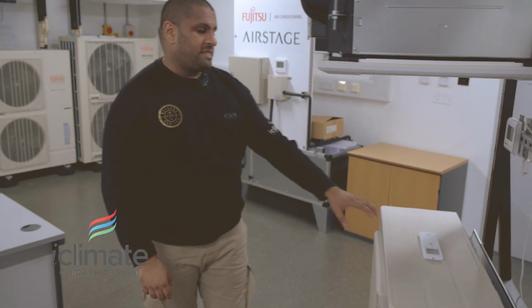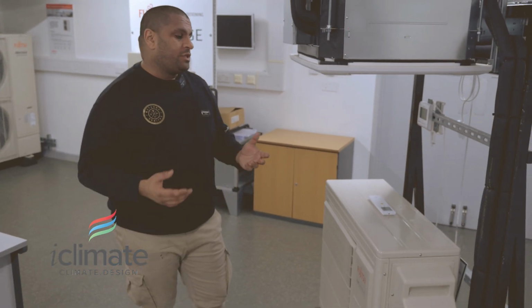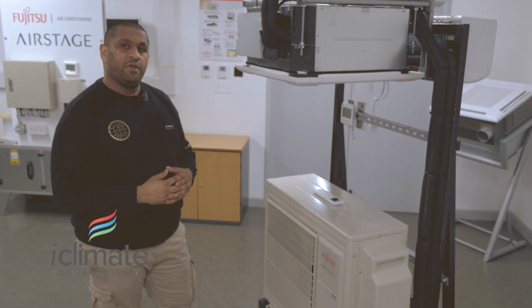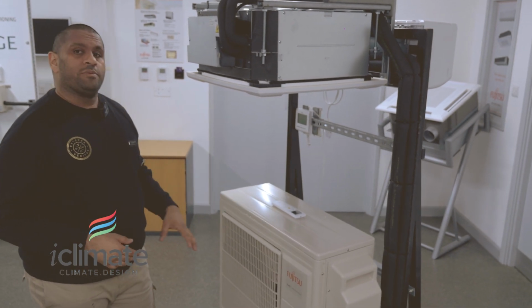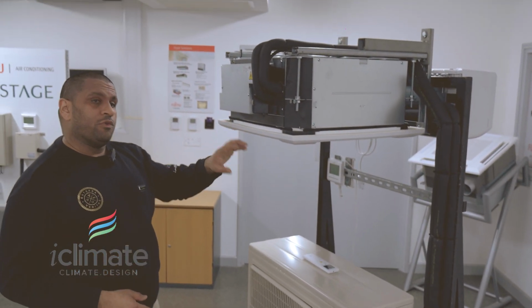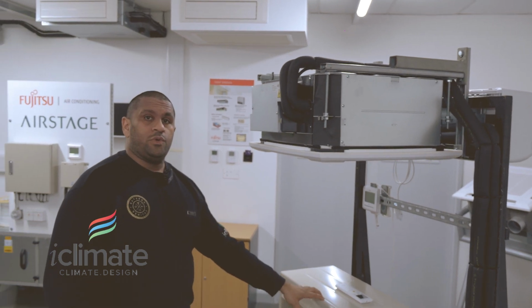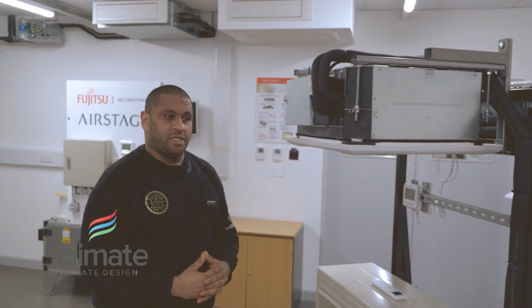So far we've been talking about air conditioning on a one-to-one basis, a split arrangement, which means one inside unit and the associated outdoor unit. The question I get asked a lot is, can I have all my air conditioning requirements done from one central outdoor unit, especially in residential properties in London? And what's next to me is this exact unit. It's the multi-type of AC condenser. It comes in a configuration of 2, 3, 4, and 5. So we can feed a minimum of 2 units and all the way up to 5 units of different type of indoor variants from one central outdoor unit, ideal for retrofit residential properties.